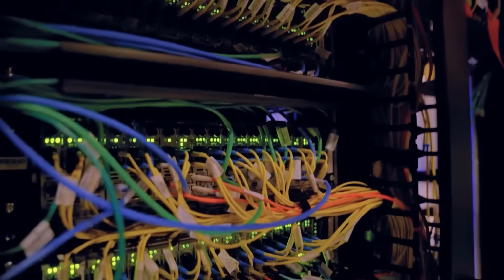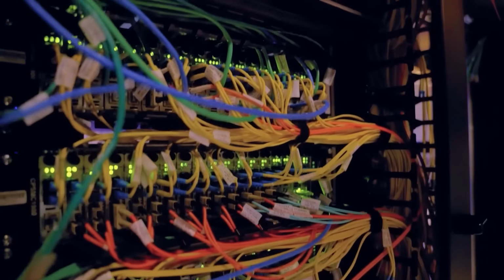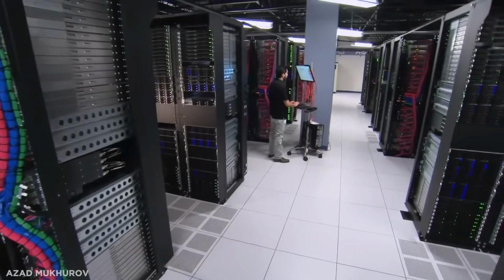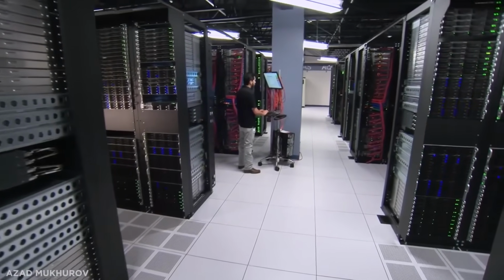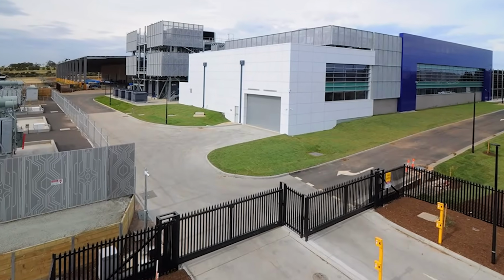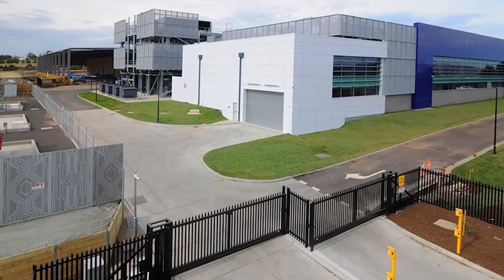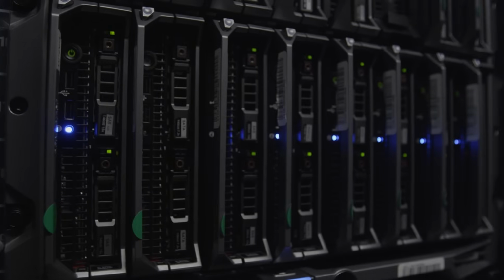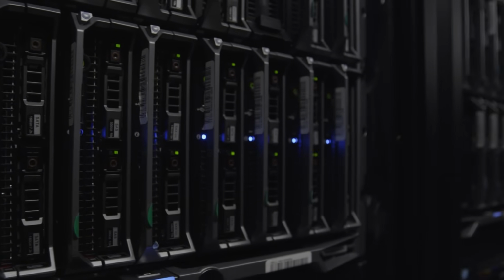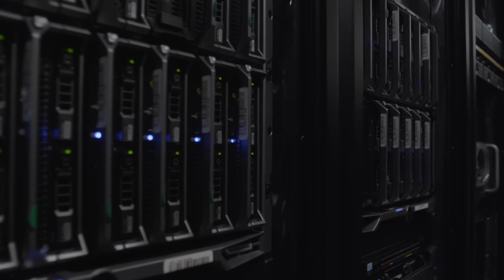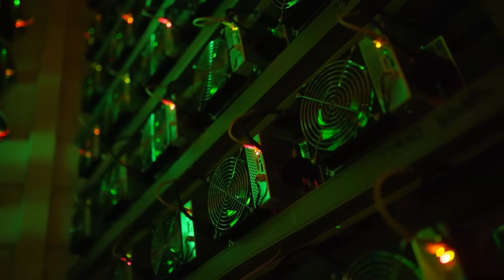The key measure of success is the power usage effectiveness, or PUE. A perfect, impossible score is 1.0. AirTrunk SYD3 is designed to achieve a world-class PUE of 1.15. This means that for every 100 watts used by the actual computers, only 15 watts is spent on cooling, lighting, and other support systems.